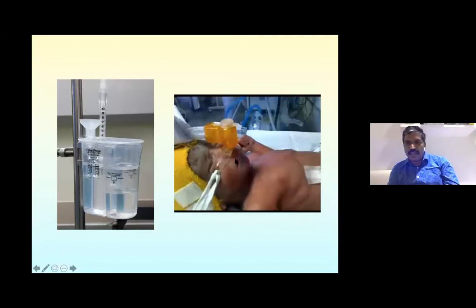Now this is another method of creating pressure. This is called a flow driven CPAP. Here there is no expiratory limb. There is only one limb, that is the inspiratory limb, and there is a pressure manometer. So whatever gas is going, it is going to the baby directly. Depending upon how much is the flow in the circuit, the pressure is built in the nasal interface. So this is the flow driven CPAP. The pressure in a flow driven CPAP is inside the nasal interface. In a bubble CPAP, the pressure is built in the bubble chamber. So I hope all of you understood.